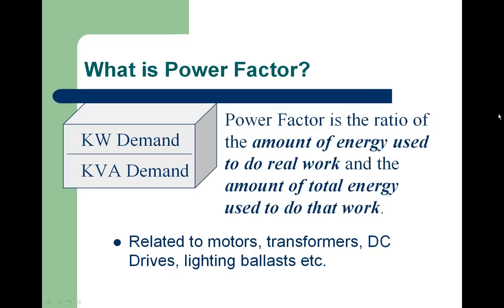Good afternoon, everybody. Again, my name is Don McQueen. I think you can all see on the screen: what is power factor? Power factor basically is a percentage. It's a ratio between the amount of real energy to do the work, which is in kilowatts, compared to the total amount of power that you're using from the utility, which is kVA.